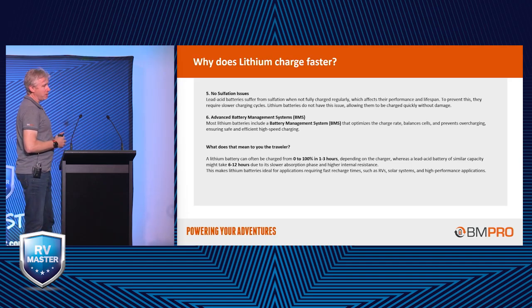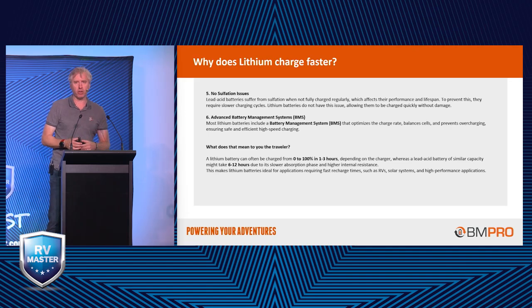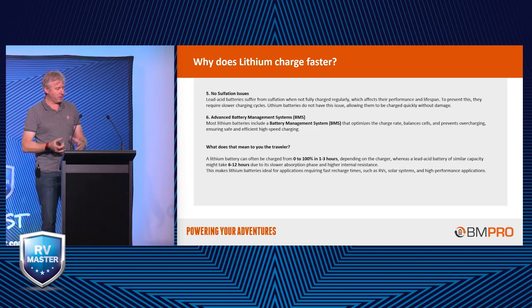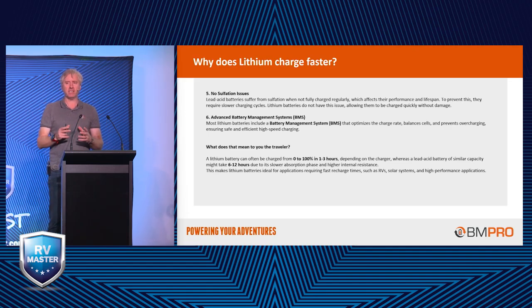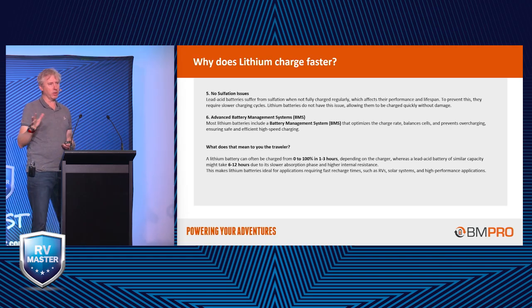And you've got an advanced battery management system. You can have a look at the one that I've got down the front here. It's not going to tell you much, a fancy green board, but effectively there are individual cells inside that battery, and it charges each one of those, or allows the charge to each of those, to be optimized depending upon temperature, etc. So if the temperature in one of the cells was getting too hot, it would slow that one down to allow it to cool, and then it would just keep charging the other ones.